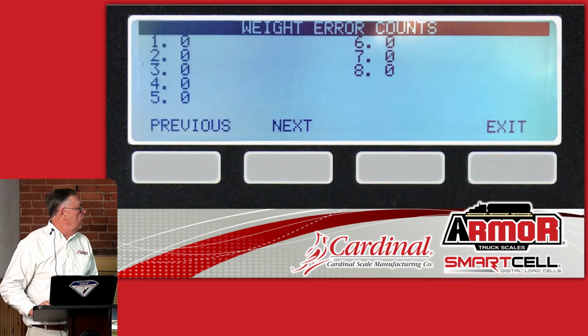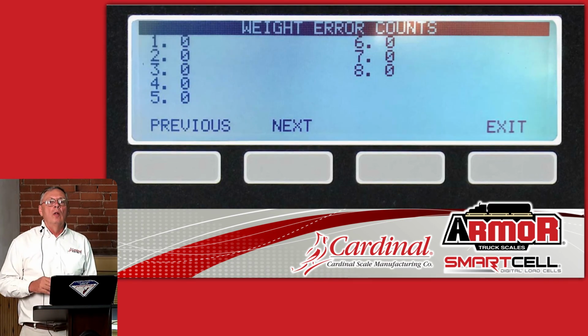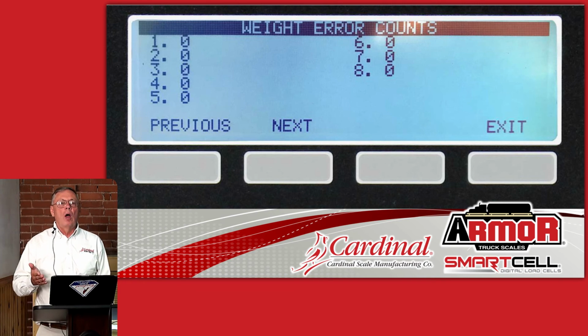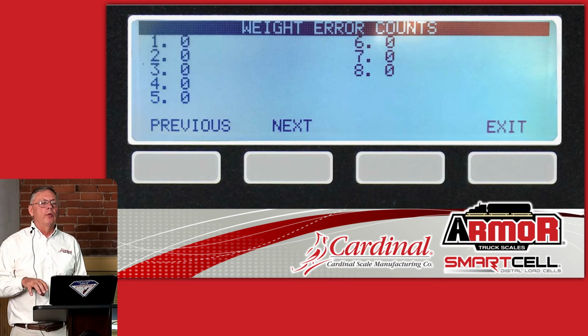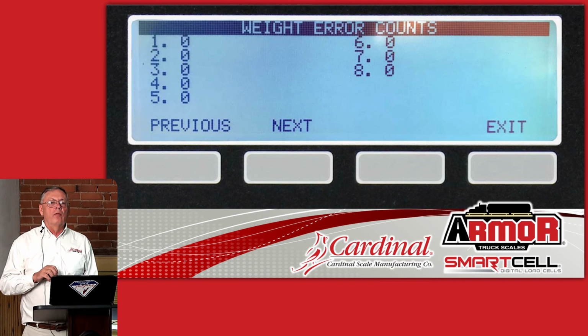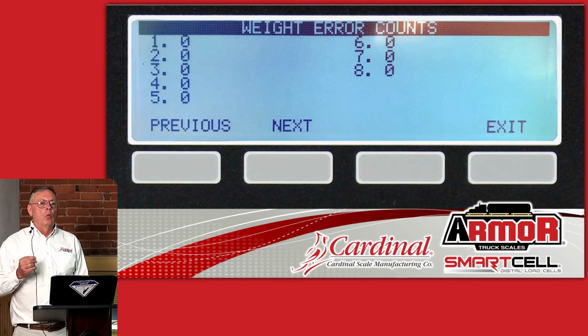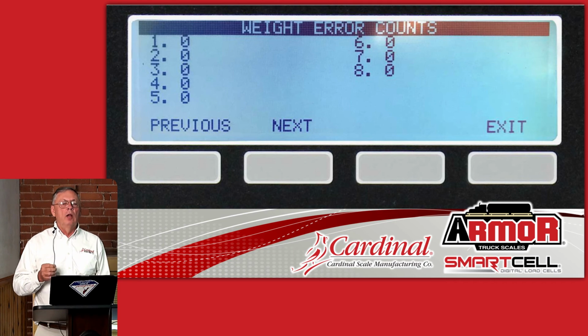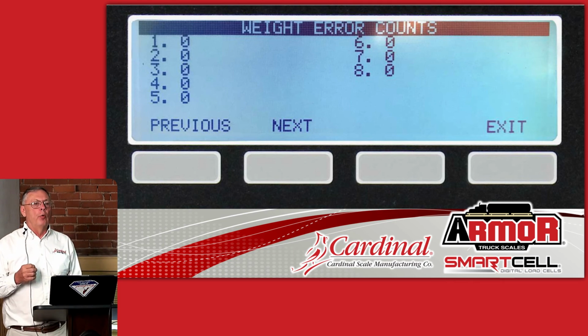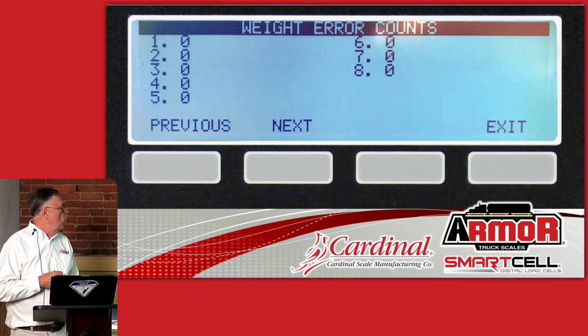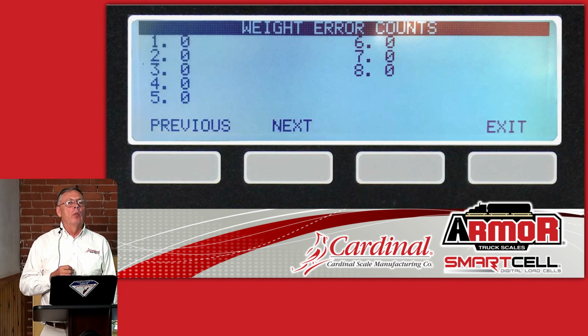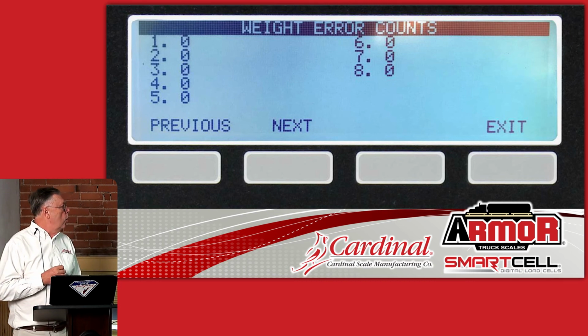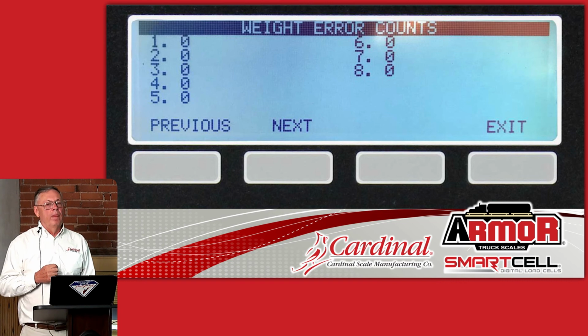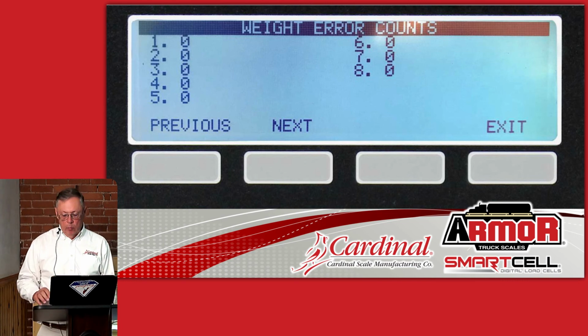The next error screen here is actually on the analog side of the A to D converter that's built into the digital load cell, where if there was an issue with the strain gauges or the circuitry, we would actually know that that A to D converter is not getting the correct amount of voltage to run, and we would show weight errors there. Normally, if you would show any large number of weight error counts, that load cell would have a problem and need to be replaced.